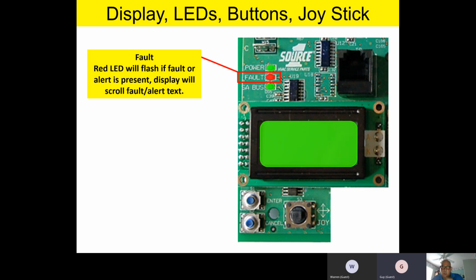But on occasion, if you take something off the SA bus, let's say you replace an economizer and it doesn't recognize the new economizer, you would go in and do what we call a relearn function, which would clear the board as if it was brand new. Then you power it back up with the new economizer, and you clear it that way. So most of the time you'll clear the fault just by fixing the bad component, and occasionally you have to go into the user display and do a relearn sequence. Then the board will relearn that it's sitting there all by itself, and when you plug the economizer on, as an example, it'll go out, see that economizer, and accept it, so to speak. So it really depends on the fault you have and how you do that. But yeah, that's a good question.